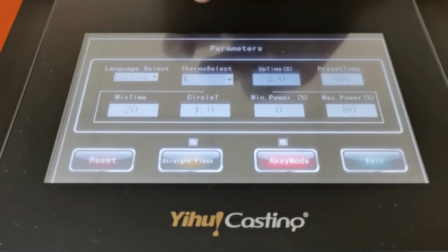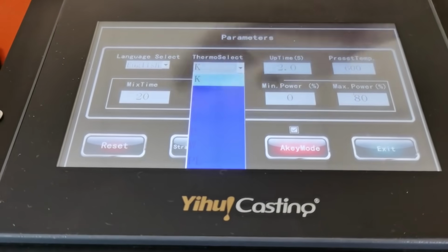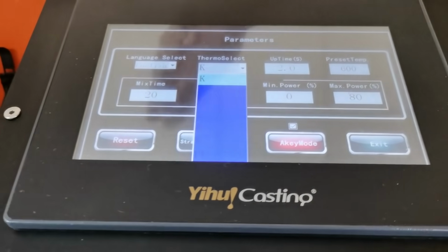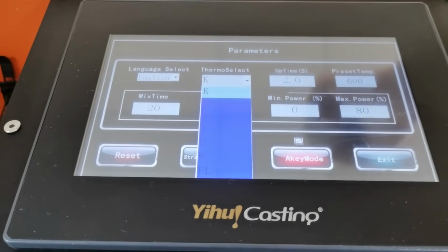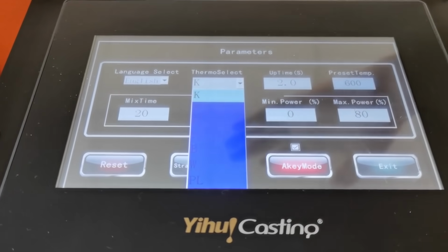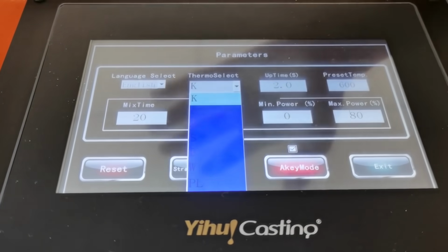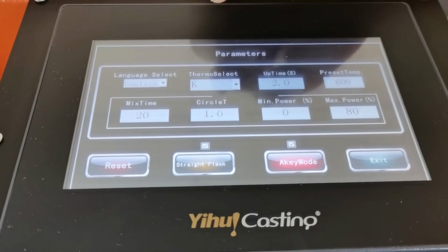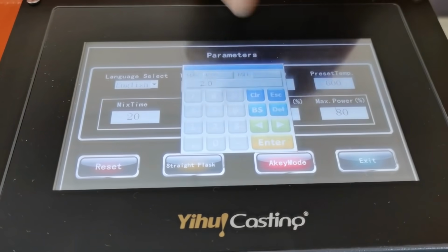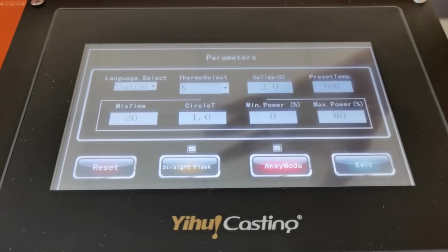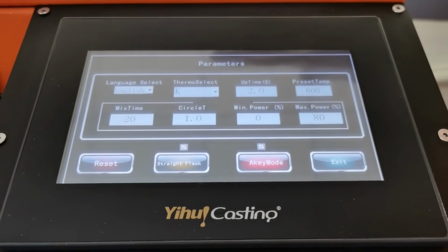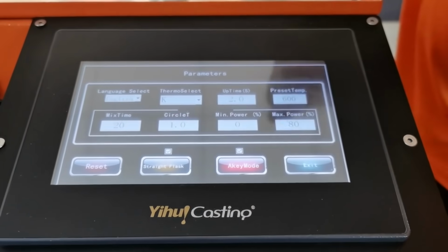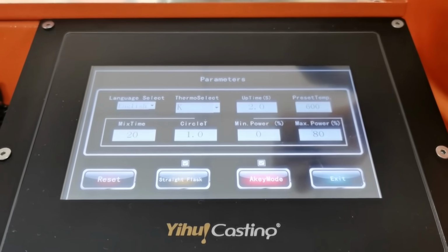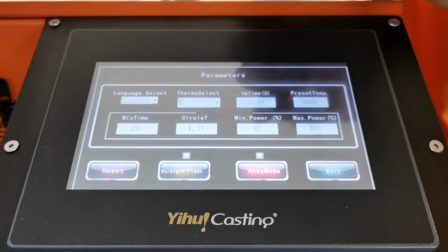Okay, then the thermocouple. For the thermocouple selection, you can see there are so many types. So before you use this machine, you need to confirm with us which type of thermocouple you use. Today we use the K type. Then the up time. For the up time, we set 2 seconds. It means when the up cover and down chamber come to the right position, the system will close automatically after 2 seconds.